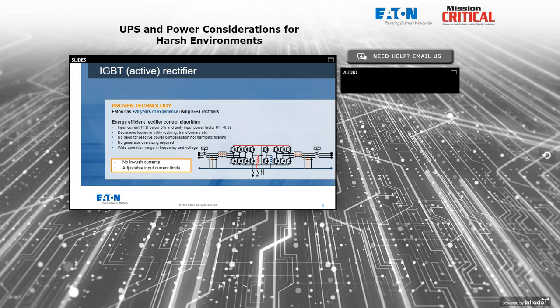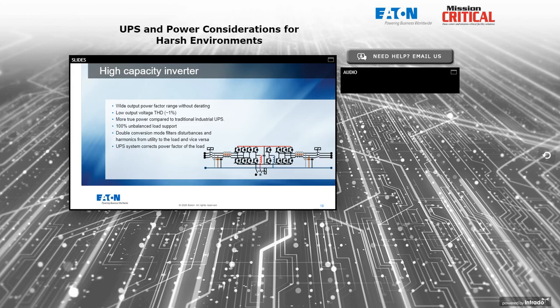So lots of advantages to active rectifiers, and not all designs, especially for industrial, are using those types of rectifiers, but the more modern devices, it is much more common. So it's a good feature to look for when you're comparing UPSs. The high capacity inverter we already mentioned, mostly to be able to handle high inrush and overload conditions. Low output voltage THD: we were talking current THD on the rectifier. The output voltage, we're thinking more in terms of voltage distortion rather than current distortion.